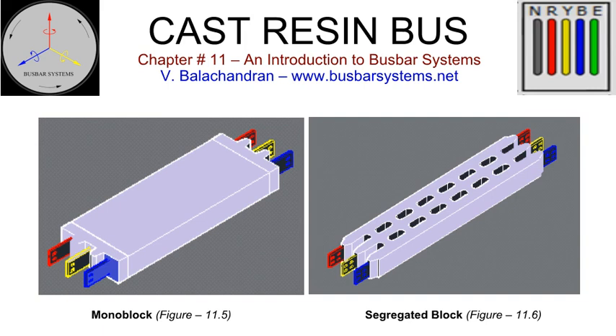2 adjacent sections of the cast resin bus are joined by fish plates. Here also there are 2 options for the protection of the site joint. The single-phase site joint can be boxed in an insulating cover when installed indoors. It can also be encapsulated in an epoxy compound at the site, using techniques adopted for cable jointing. Standard bends, elbows, tap-offs, and termination ends are available for various current and voltage ratings.